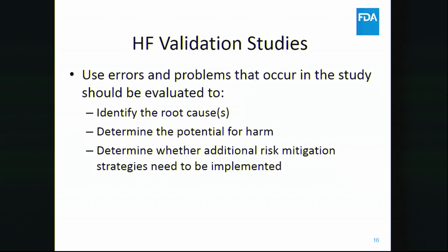So in terms of validation studies, what we ask companies to do is to look at evaluating these products using representative users, the actual users who would use these products themselves in the market, and walk them through the use tasks or the scenarios of using the product, and identify what are the areas that we see people are having difficulties with. Where are we seeing observations where there may be errors that are occurring? And basically be able to dig down and say, okay, we observed this happening.